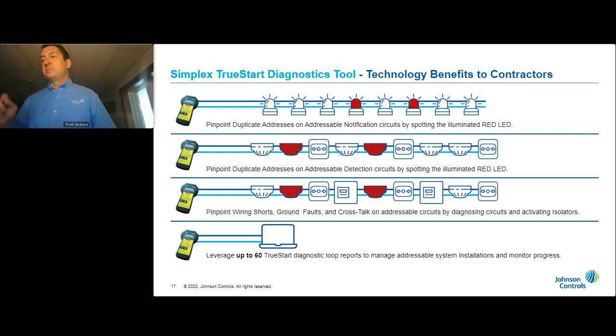Same thing on the addressable notification, which is what Brian talked you through. Again, we can detect where we have duplicate addresses and change those addresses based on the test results of your field wiring. And then your fundamental testing, where you're looking for shorts, looking for grounds, our meter will also tell you if you're going to have a crosstalk condition in the wiring plant that's been installed.